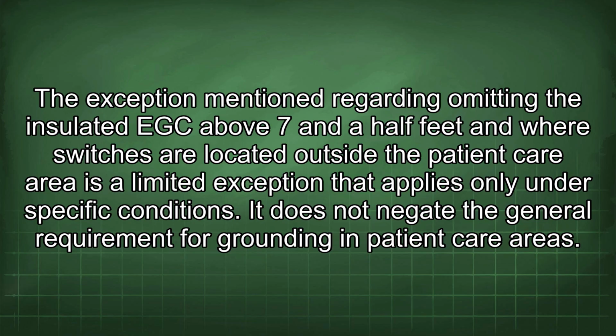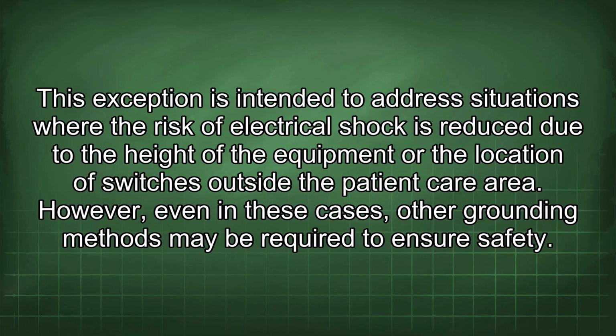The exception mentioned regarding omitting the insulated EGC above 7.5 feet and where switches are located outside the patient care area is a limited exception that applies only under specific conditions. It does not negate the general requirement for grounding in patient care areas. This exception is intended to address situations where the risk of electrical shock is reduced due to the height of the equipment or the location of switches outside the patient care area. However, even in these cases, other grounding methods may be required to ensure safety.